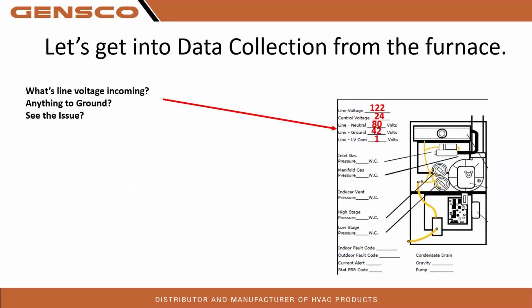All right. So as we start doing data collection from the furnace, we can look at, as we start applying the info to the sheets, right? So in this situation, we've got 122 volts. If you were to look at it from black to white, we have control voltage of 24 volts, so that's good. So we got a transformer that's hot and making what we need.